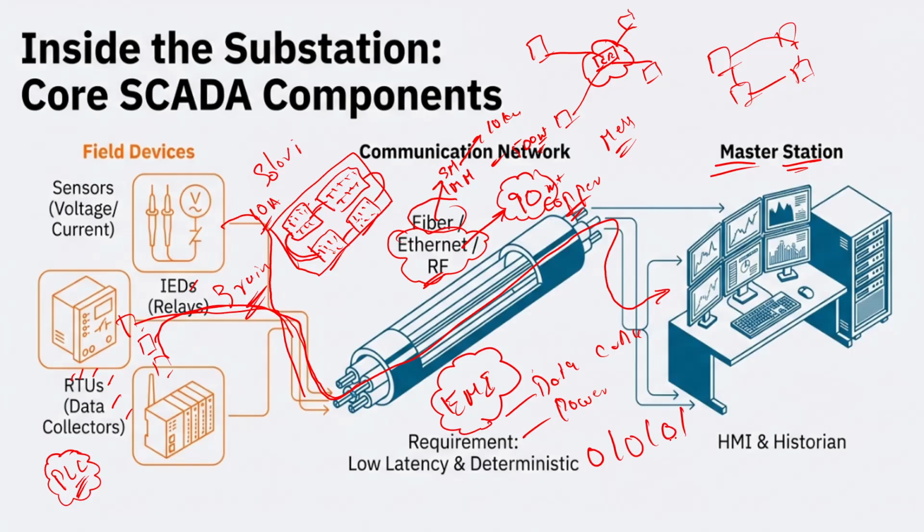So this is how digital data looks, and this data will be packeted and channeled through the cable. It could be an Ethernet or the fiber. So when you are running the data and power cable together, the data can be missed, or else it can get corrupted. So it is always recommended, and it is good practice.